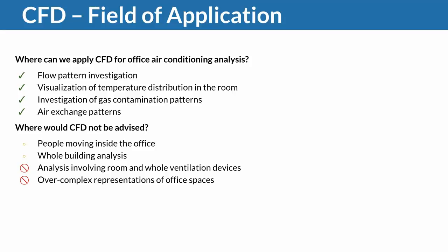Keep in mind that so far, and whenever you read through most of the available standards, for example ASHRAE standards, they are very specific when it comes to the overall bulk approach to the problem. You need to supply X amount of cubic meters of fresh air every hour for every person in a room. And yes, you should ensure that inside the office you do not have a draft of 0.2 meters per second, so that people don't feel cold. But at the same time, these are very broad terms.